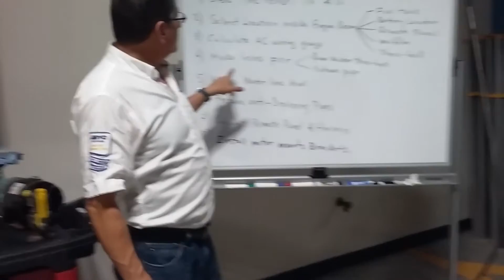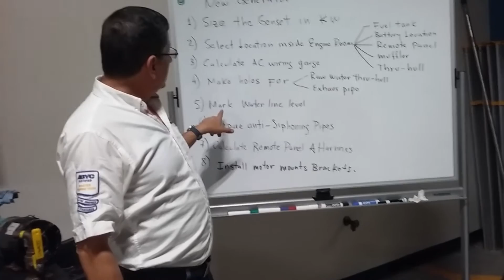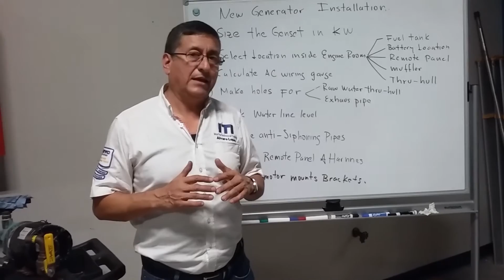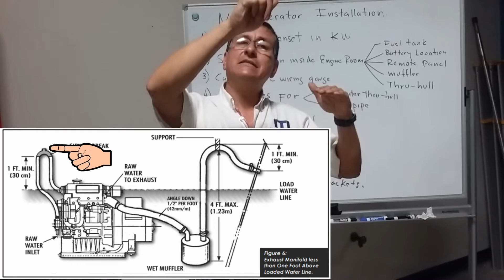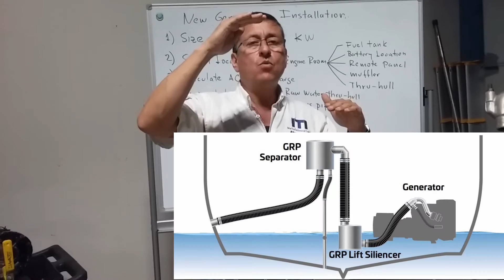The next step is to make the holes for the raw water and the exhaust. After that, mark inside the engine room where the water line should be located. The water line is critical, because if the new generator is installed below the water line, I probably need an anti-siphon. If it's located above the water line, I probably don't need one.